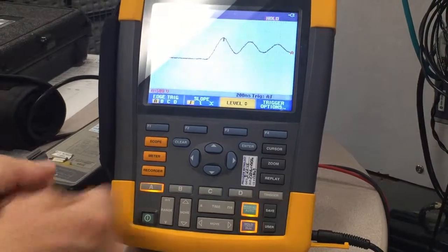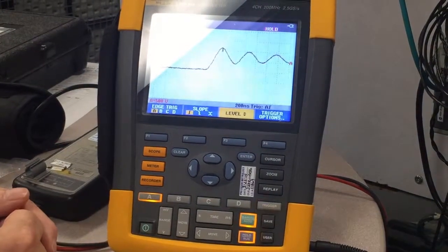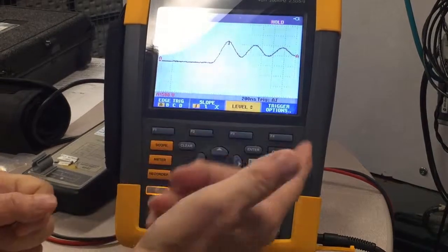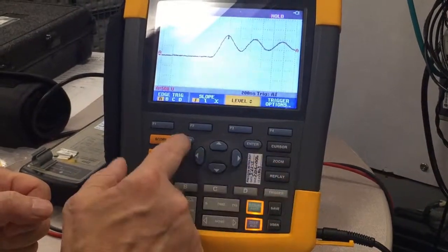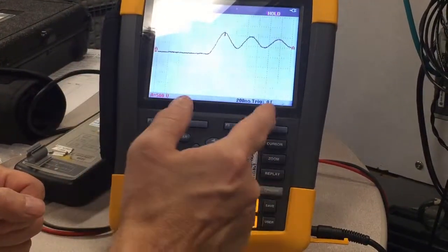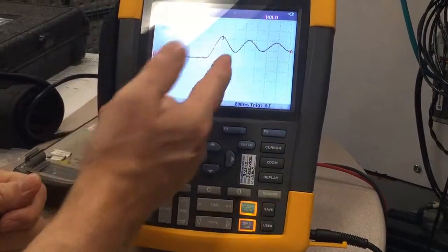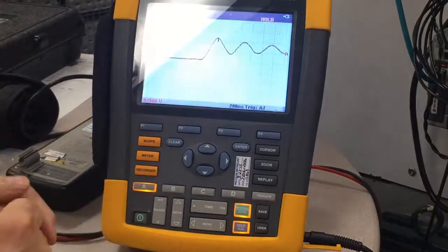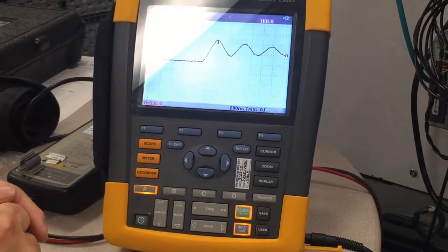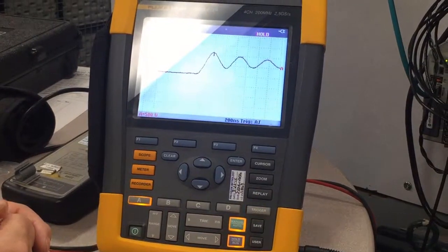We stopped it. It's on hold. And that is one reflective wave voltage with a rise time of approximately 200 nanoseconds and a peak value of just over 1,000 volts. So, there you go. That is how to set up a Fluke scope meter to capture reflective wave voltage. Thank you.